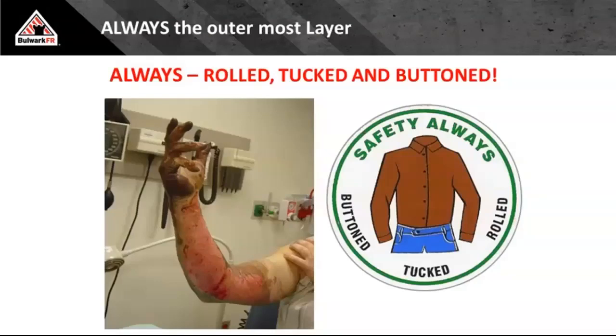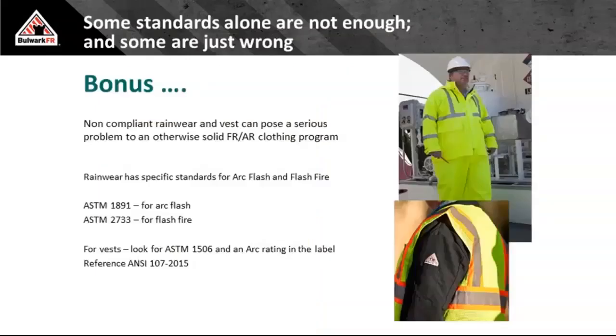That safety sticker adorns a hard hat in Southern California to remind all their electricians how to properly wear it. This picture here is a very, very difficult reminder of failure to verify. His arc-rated shirt worked perfectly. You can see from mid-bicep up, he rolled up the sleeves of his arc-rated shirt. He doffed his rubbers for shock protection, his leather protectors to protect the gloves, took off all his PPE, and when he put that screwdriver inside that MCC, it was not de-energized as he thought. That whole career changed literally in the blink of an eye, and it didn't need to happen. So be cautious.